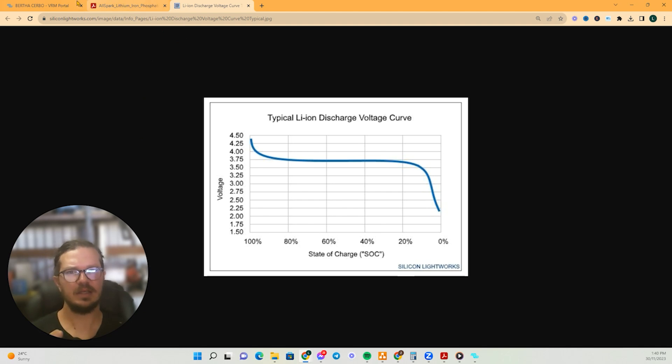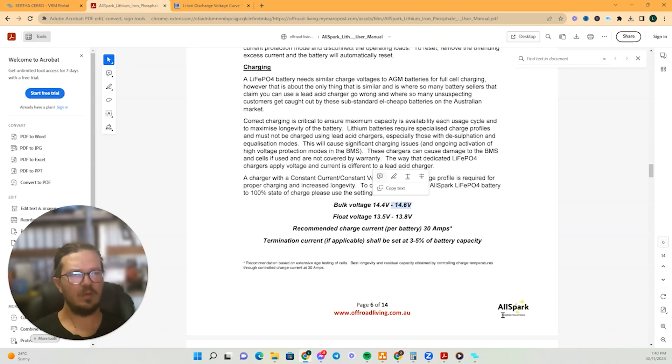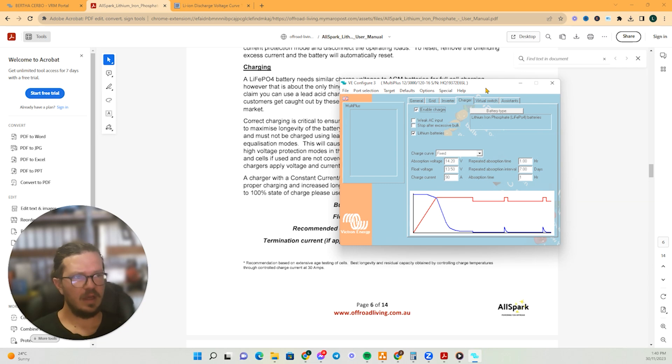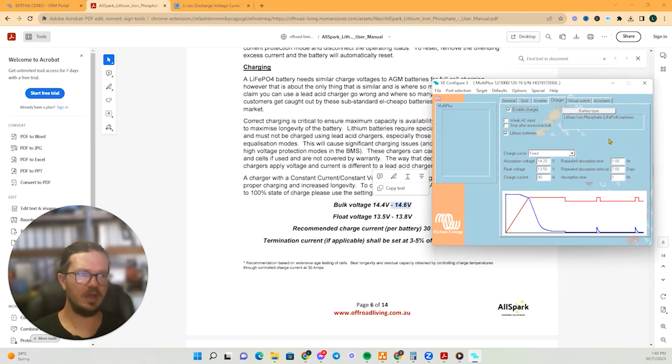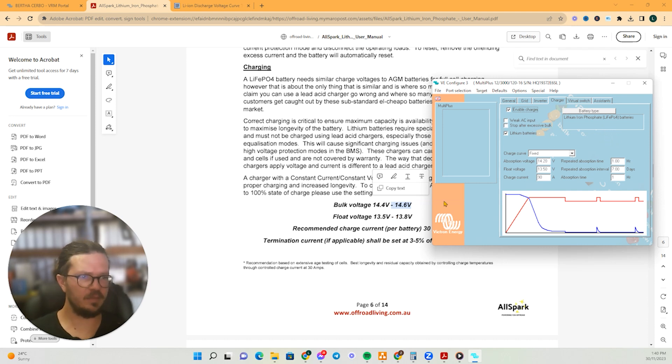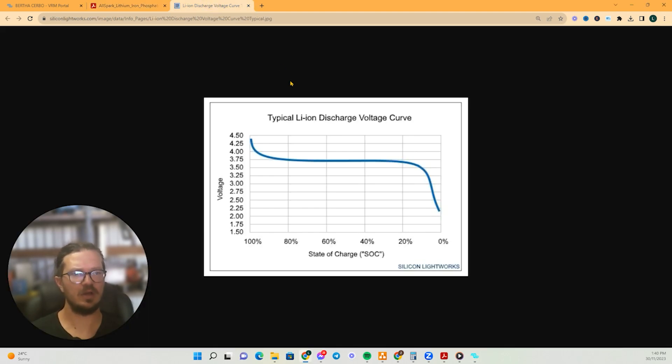So that and that's why these settings are important to get right. So I will go back to here. So this is the settings and this is how it's been set up for this gentleman that's having problems and see this, like the absorption voltage. So that's 14.2 is what that was set at, which is way too low.